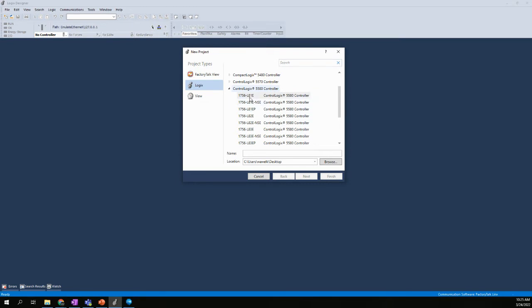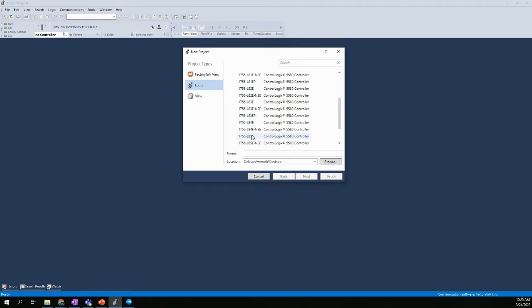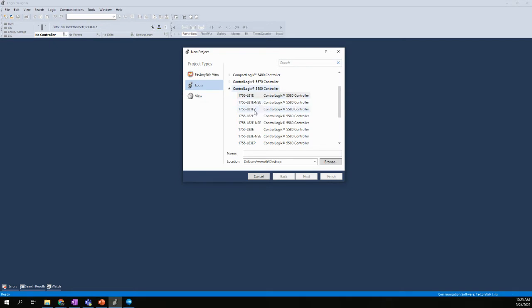Now, you have options. You have several options of the 5580 processor. There's a L81, L82, L83, L84, and L85. The only difference between these are the amount of memory that each processor has. So it doesn't really matter, but I would go ahead and just pick the L81E. The E stands for Ethernet. The NSE stands for no storage, no stored energy device. The EP stands for process controller. So we don't need to worry about these two, the NSE or the EP. We'll just stick with the base L81E processor for our exercises.